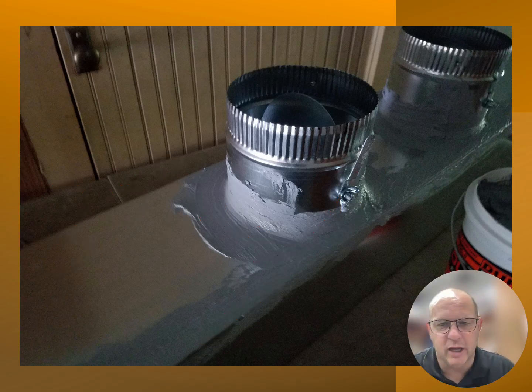So seal that ductwork up. Don't use tape. Use the mastic. I know it looks like crap, especially when you're dealing with open ductwork that doesn't have any insulation on it. This stuff, we're insulating it. It doesn't matter what the mastic looks like on the bottom side of it. We're going to cover it up with some nice foil back fiberglass insulation.